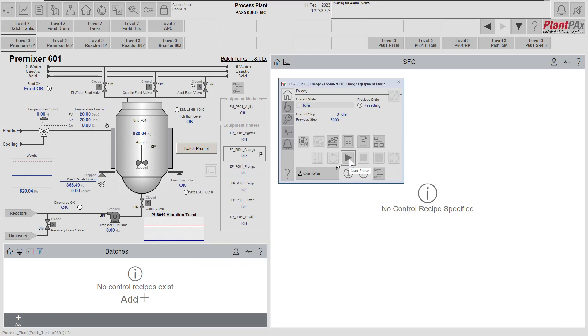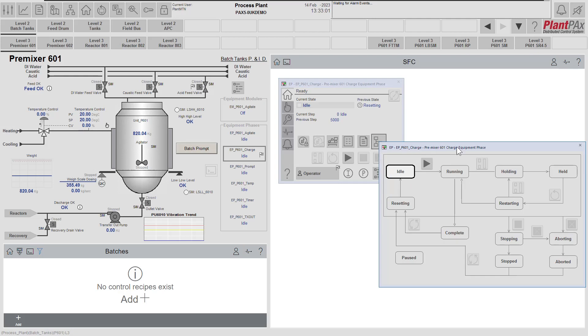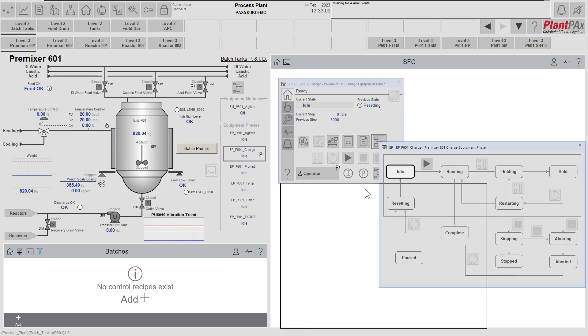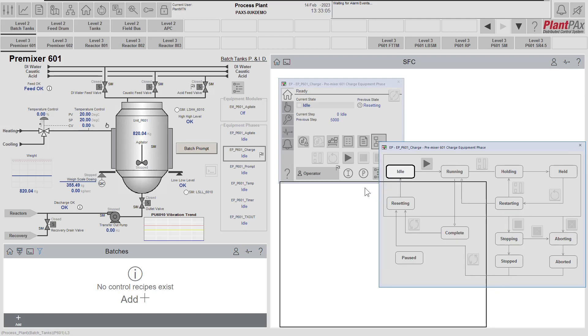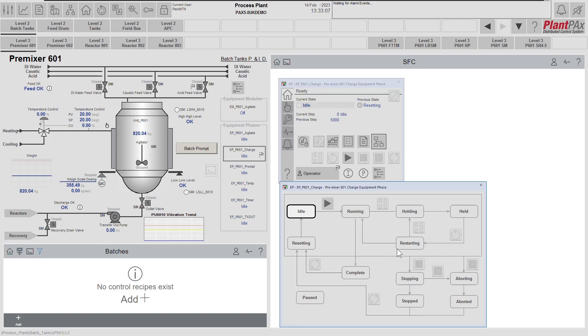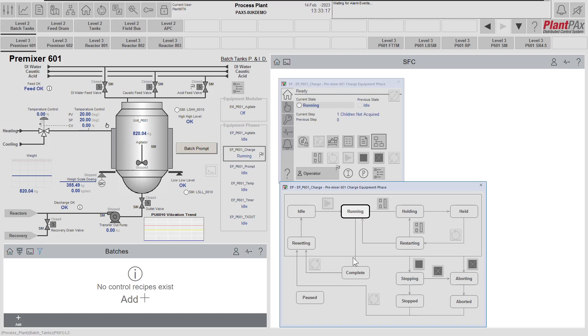Then I'm going to go and run the equipment phase, which we can do directly from the faceplate using the start phase button. We can also show the detailed state display where we see the ISA S88 equipment phase state model and can control it from this faceplate as well. So let's start the phase and we'll see that the phase transitions into the running state.